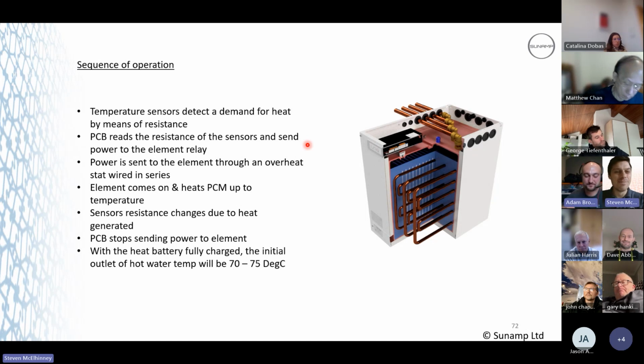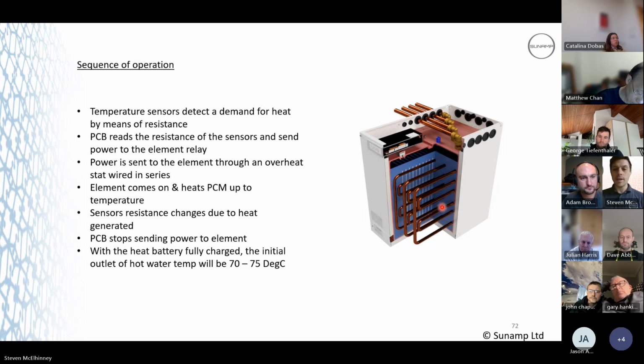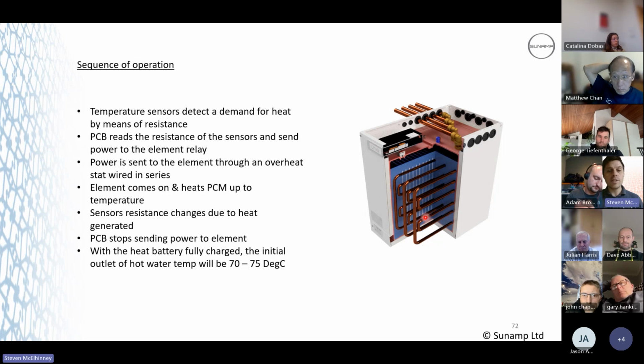So yeah, basic sequence operation here. Back to this cutaway. The temperature sensor, which is here, goes all the way down to the bottom there. Put power on, pressurize the heat exchanger. Temperature sensors detect a demand for heat by means of resistance. We've got 3 NTCs in here, and they'll be obviously high resistance, say 12 kiloohms. That's generating a demand. So the PCB reads the resistance of the sensors and sends power to the element relay.